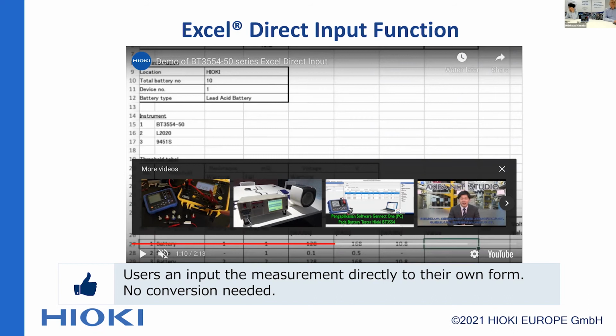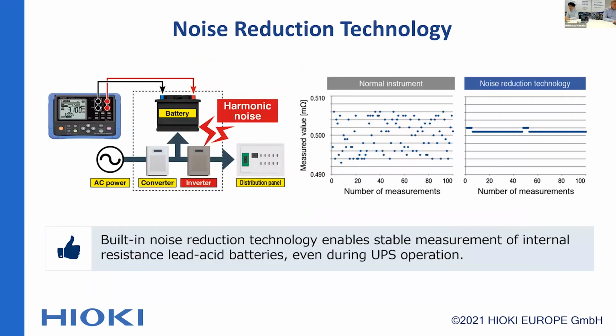Unique selling point: noise reduction technology. Our battery tester has high noise resistivity during UPS operation. There is harmonic noise from the inverter. If the frequency of the inverter noise is close to the measurement frequency of the battery tester, a stable measurement is not possible. To solve this problem, HIOKI developed a noise reduction technology.